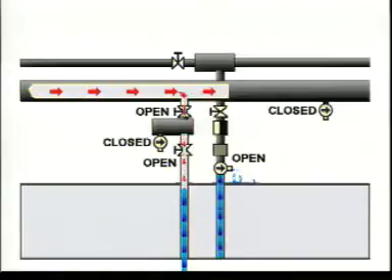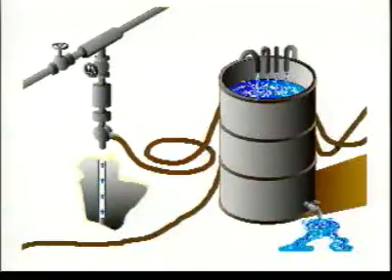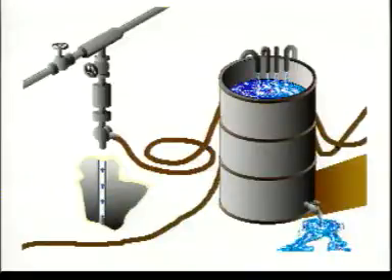Consider the volume of a coil and measure the amount of water passing through the drain cock per minute. It is not enough to flush a coil for 10 to 15 minutes. You can probably flush several coils at the same time, but supervision, checking for traces of oil, is difficult, especially at night.